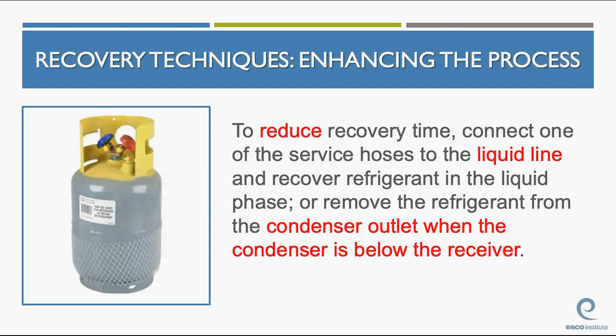To reduce recovery time, connect one of the service hoses to the liquid line and recover refrigerant in the liquid phase, or remove the refrigerant from the condenser outlet when the condenser is below the receiver. Guys, that last statement is extremely important in here.